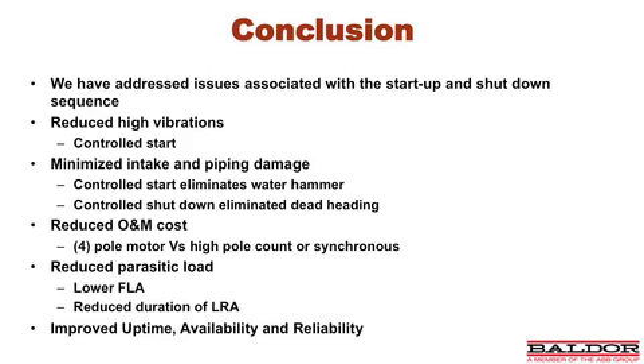We've addressed the O&M cost, utilizing a 4-pole motor versus a high pole count synchronous motor. Now, we didn't go into details on this, but many of you well know a 4-pole motor repair is far cheaper than a repair/rewind of a high pole count motor, or certainly a synchronous motor. We have also reduced parasitic load due to reduced full load amps and reduced duration of locked rotor amps. And overall, we have improved the uptime, availability, and reliability of your circ water pumping system.